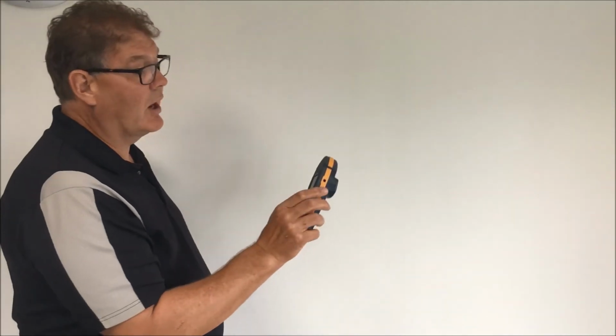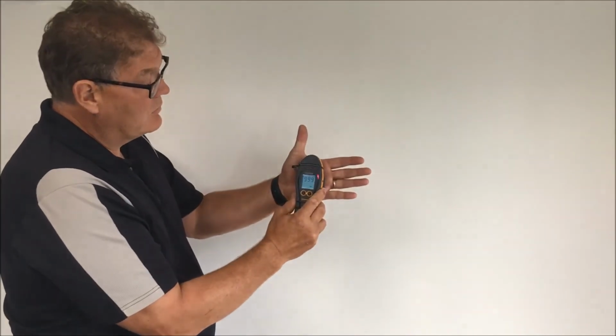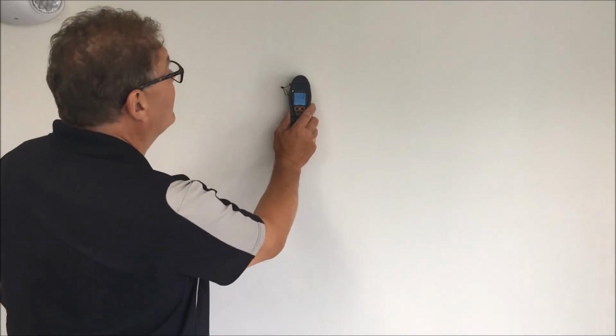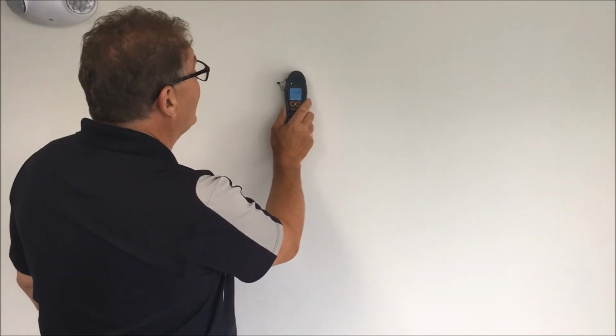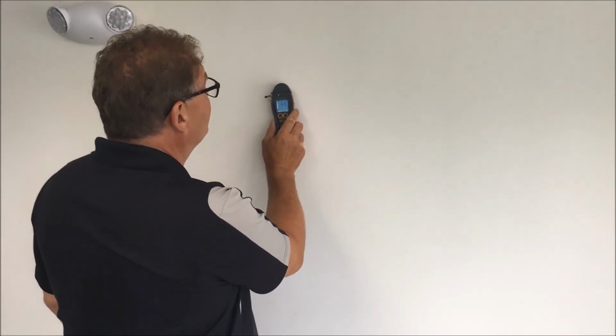We'll now change to our non-invasive mode here, and we'll place that on the wall here. Now we are seeing slightly elevated readings here as we move across the moisture, but remember, the meter's only measuring that thin film of moisture on the surface in respect to the rest of the material up to 3/4 of an inch below the surface.